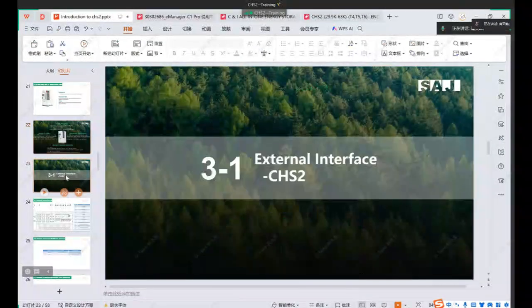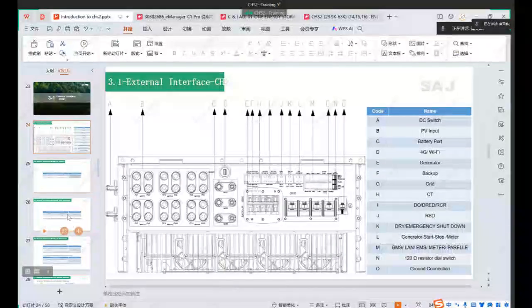So let's go ahead for the external interface. As you can see, the code A is the DC switch, and the code B is the PV input. We have 6 MPPTs, 1, 2, 3, 4, 5, 6, and each supports 2 strings, so 12 strings. When we connect the PV cable, if you only have maybe 10 strings, this one is full, but another two supplies, this is one string, and this is another string. That means connect all the MPPTs as best as you can.